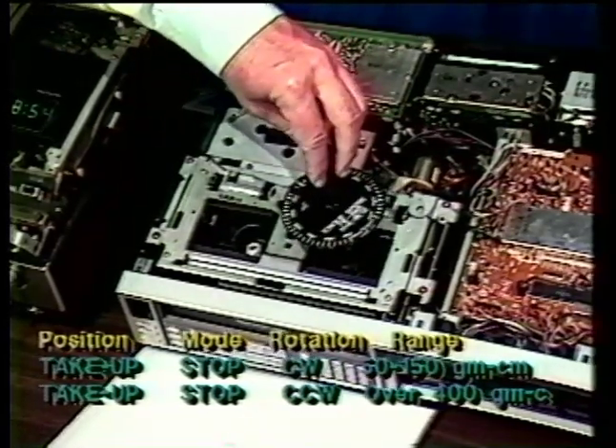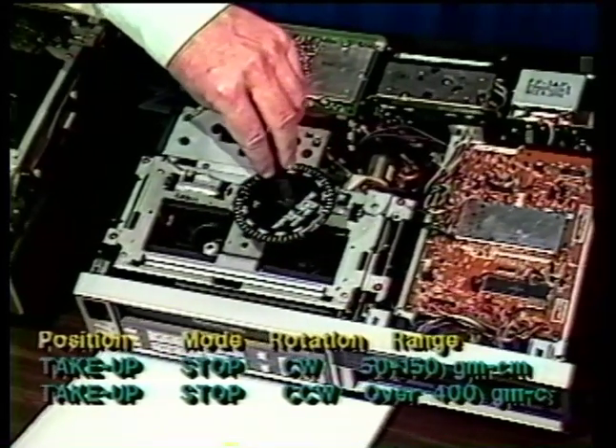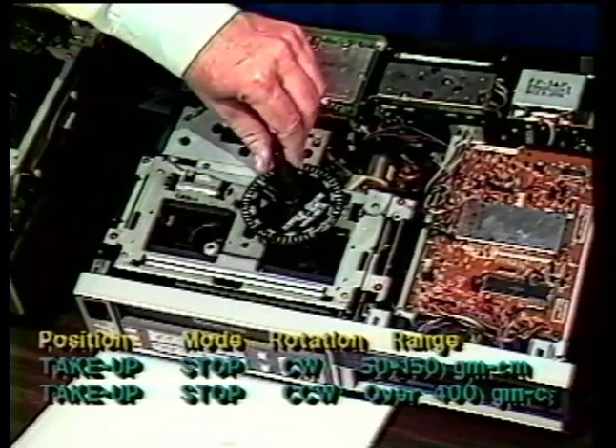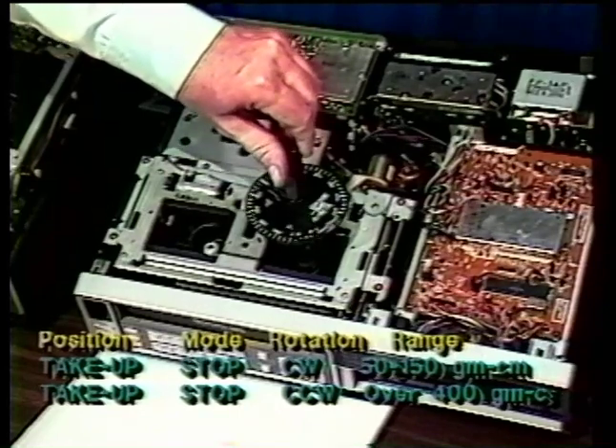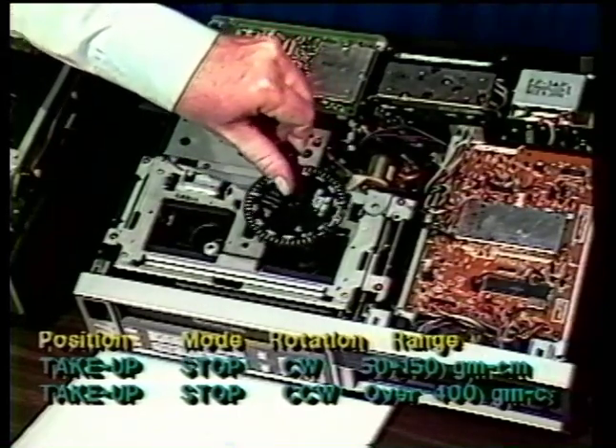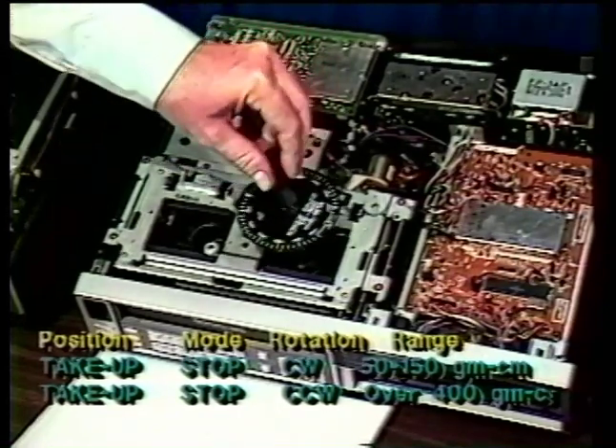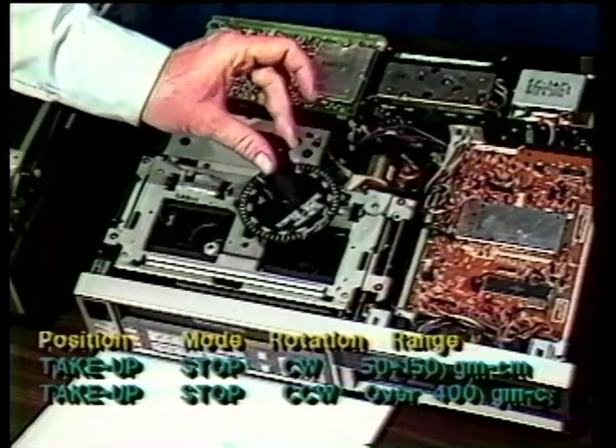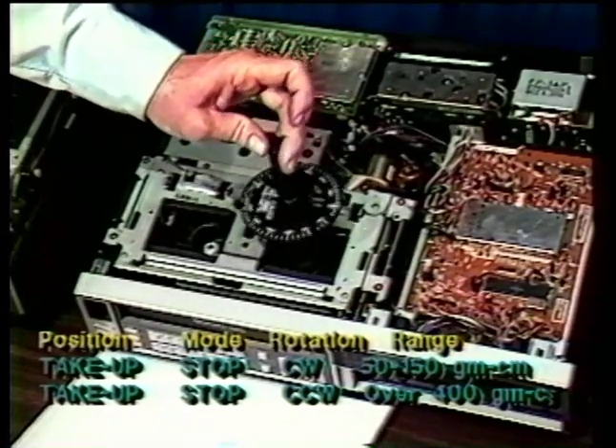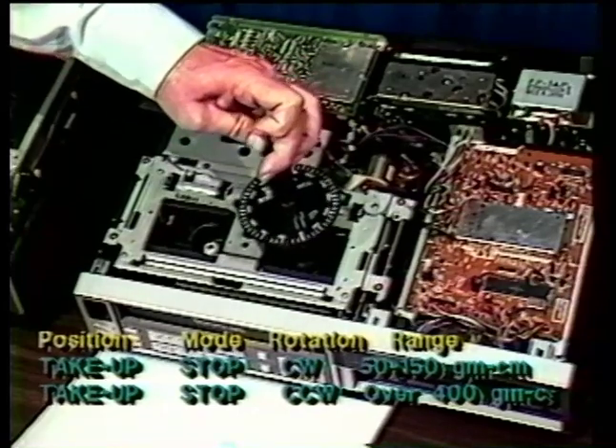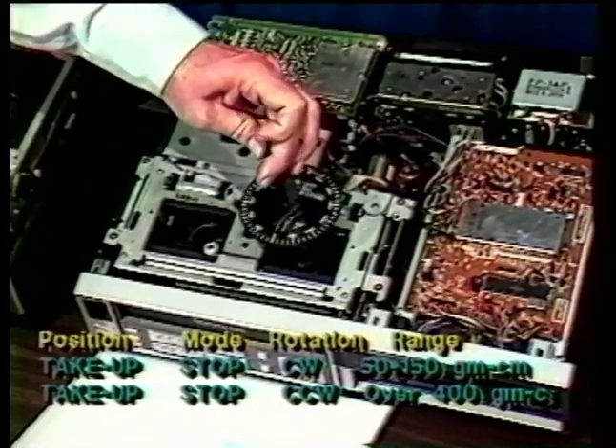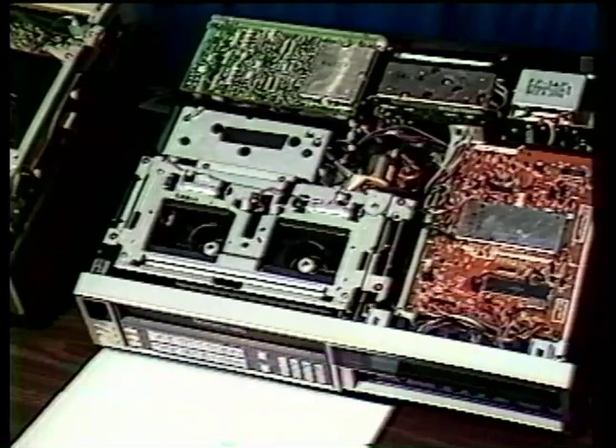On the take-up spindle, it's just the opposite. In the counterclockwise direction, it should be a high torque reading. You again see it going up to almost 600 gram centimeters before it starts slipping. The clockwise direction, again, it's about 125 to 130 gram centimeters. Both of these readings would fall on the chart.